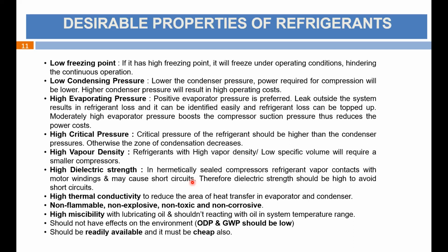And high vapor density. High vapor density means a low specific volume. So high vapor density requires a very small compressor. The size of the compressor and the heat exchanger is reduced by using high vapor density, mass per volume. High dielectric strength. This property should be there so that there is no short circuiting; dielectric strength should be high to avoid any kind of short circuit. High thermal conductivity. As you know, thermal conductivity times area is equal to the total heat transfer for any heat exchanger. This is very basic physics. So if the thermal conductivity is high, we require a much smaller area of evaporator and condenser.